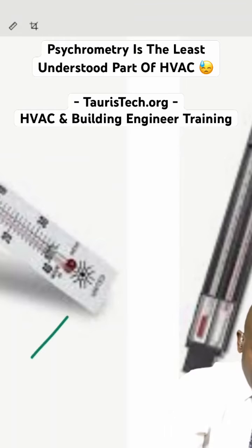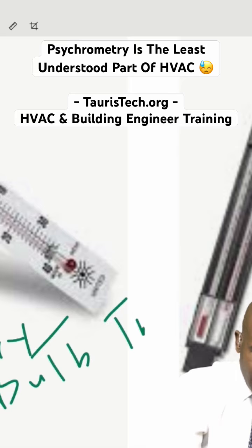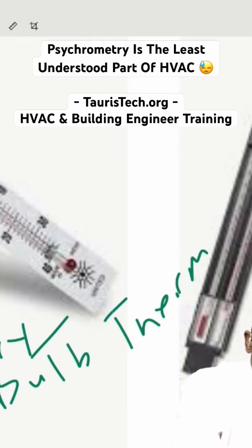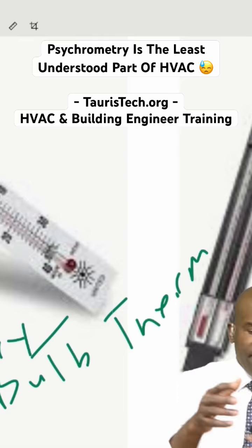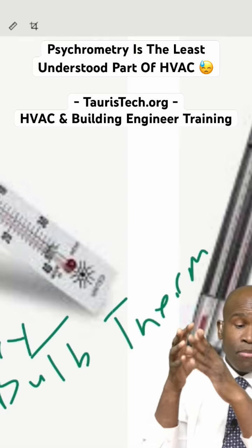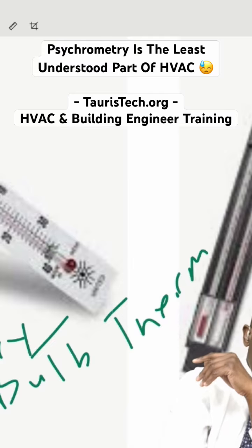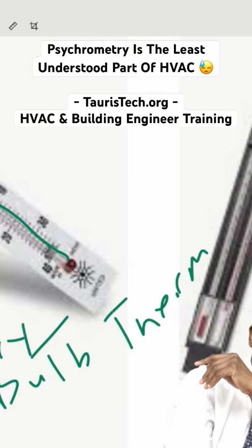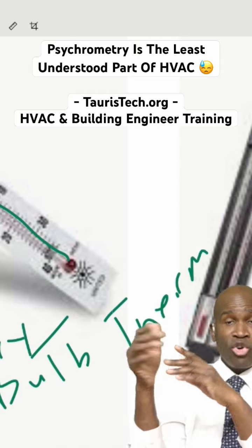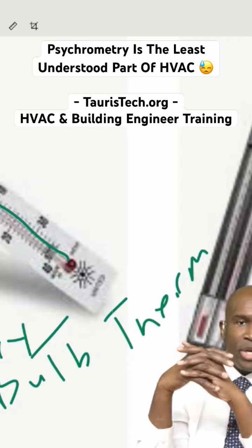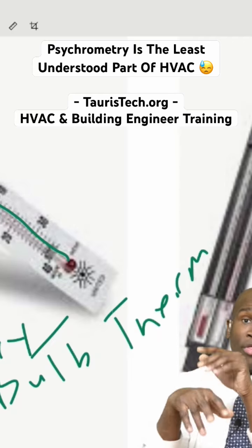This is our dry bulb thermometer. Then over here, this is our wet bulb thermometer. And if I am able to evaporate some of the moisture from that wet cover, let's say my temperature is all the way up here on the dry bulb, depending upon the amount of moisture I am able to evaporate, that is going to determine the reading on the wet bulb.